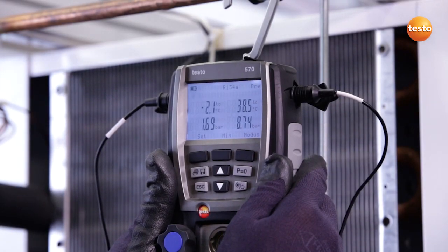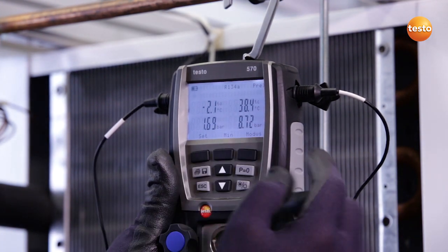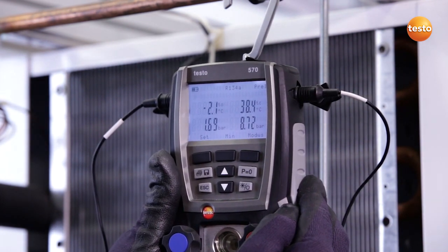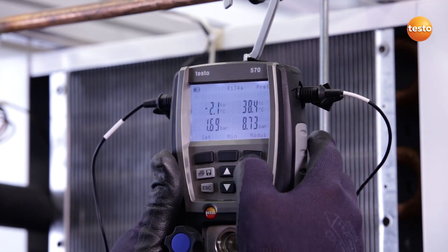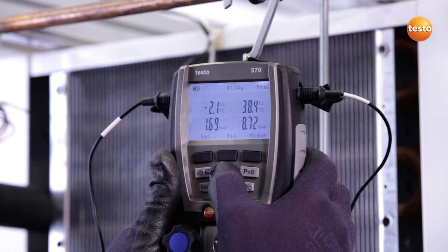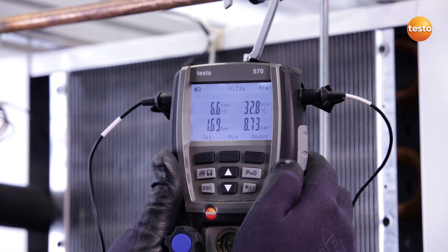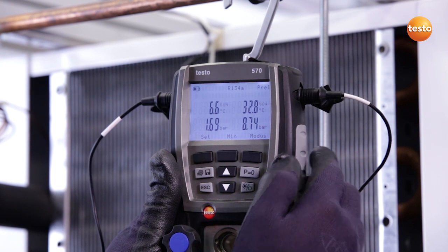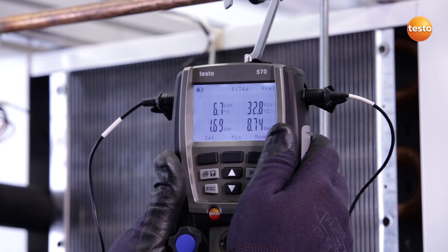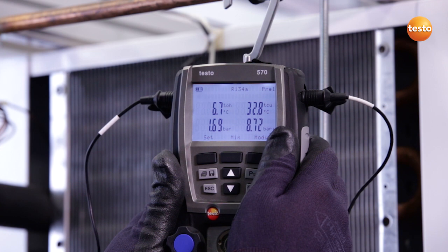The system is now in a steady state and on the left-hand side we can see our suction pressure. On the right-hand side the high pressure and the corresponding saturation temperatures — in this case, -2.1 degrees Celsius evaporation temperature and 38.4 degrees Celsius condensation temperature. This suits the ambient conditions very well right now, and by pressing this button I can also see how the probe temperatures can be read out. On the one side we have a temperature of 6.7 degrees Celsius at the exit from the evaporator, and the liquid temperature of 32.8 degrees Celsius at the moment.